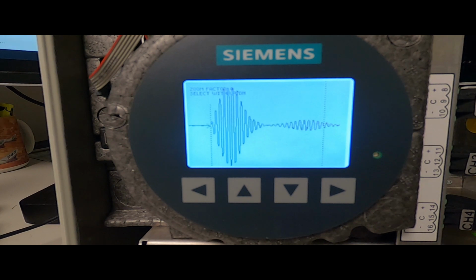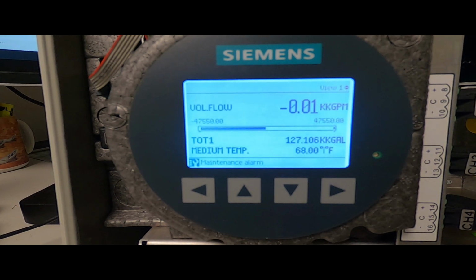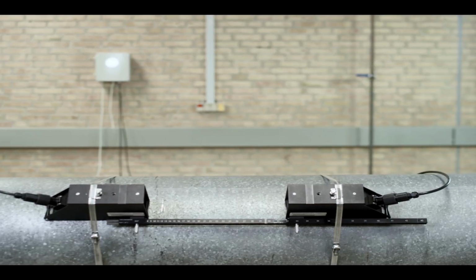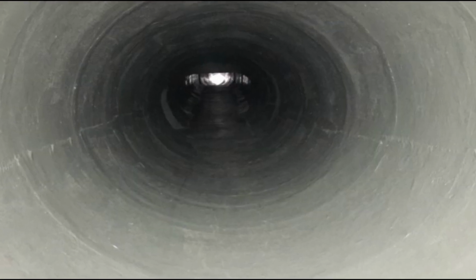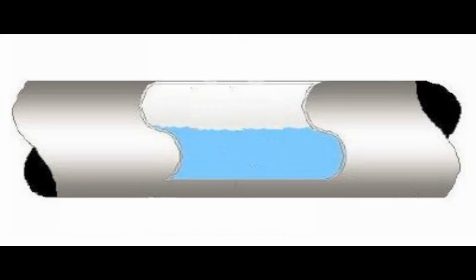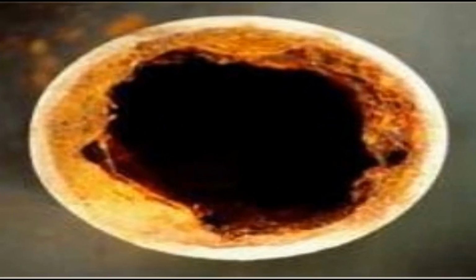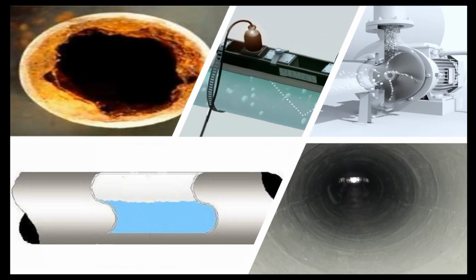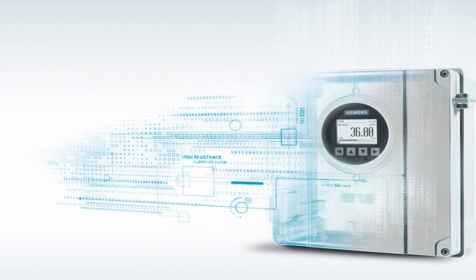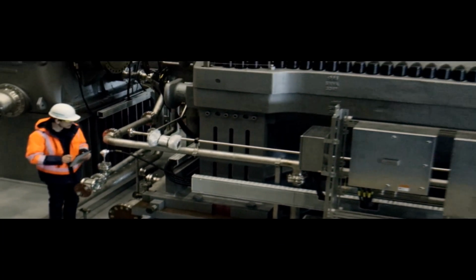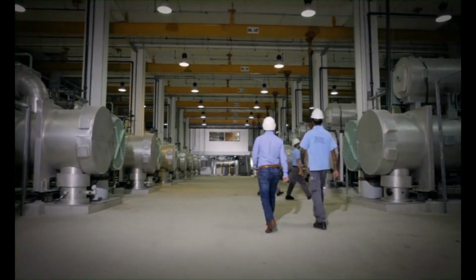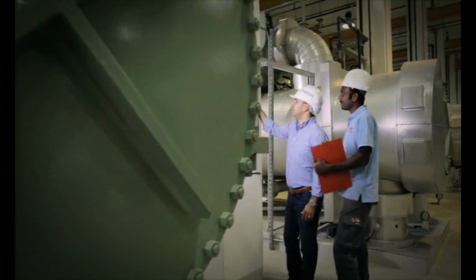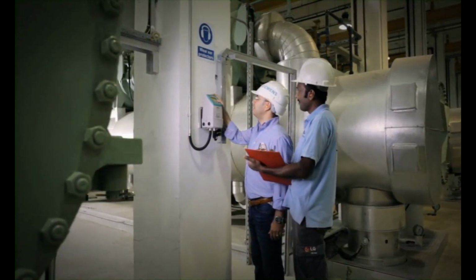Successfully achieving operation as described further identifies that the meter's inability to measure on the fluid application is due to unacceptable application conditions, such as an empty pipe or partially filled pipe, a highly aerated liquid, a cavitating pump, or excessive fouling of the inner pipe wall. All of these conditions can potentially prevent the transmission of the sonic beam through the flow stream, and it is not a fault of the flow meter. Having separated the meter from the application and confirming its integrity, you can now look into taking corrective action to improve the application conditions, which will enable proper flow meter measurement.